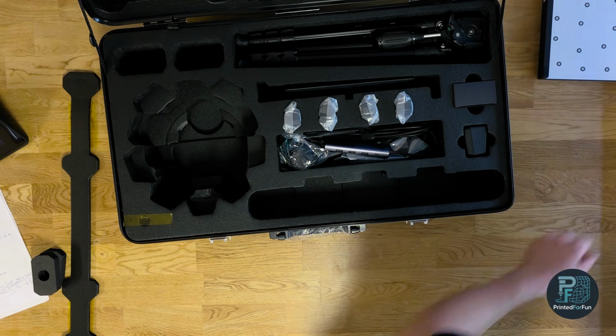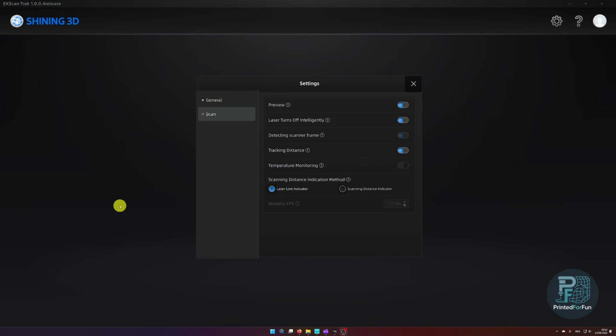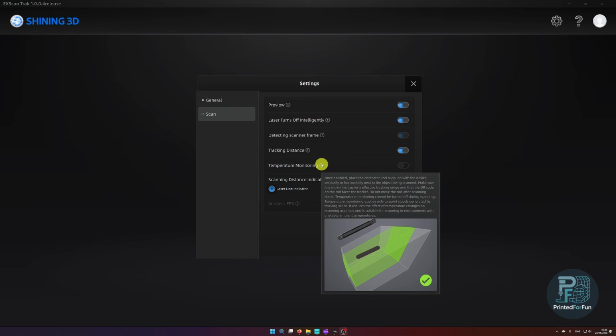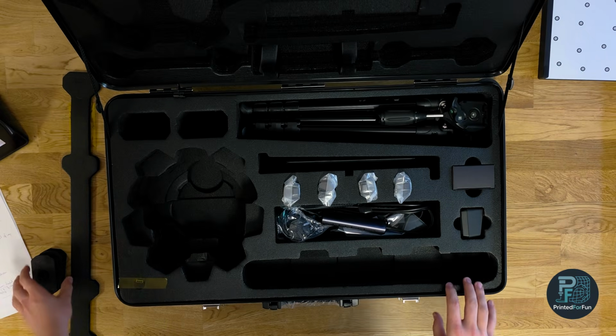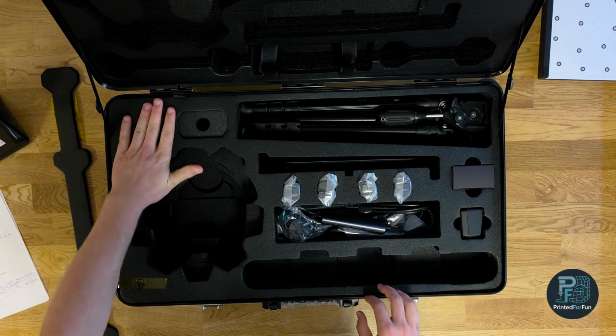So let's also put it to the side. Quick update from the future: I finally found out what the two bar holders are for. Buried in the software, there is the option for temperature monitoring. If you go to the information bar, you place the calibration pole next to your part while scanning, and then in real time it reduces the effect of temperature deviations. So finally, this isn't advertised in the manual or on the website, or at least I haven't found it, but this is a very convenient feature. I haven't needed it yet, but good that it is there. And now we can continue. So I will insert the foam back there.